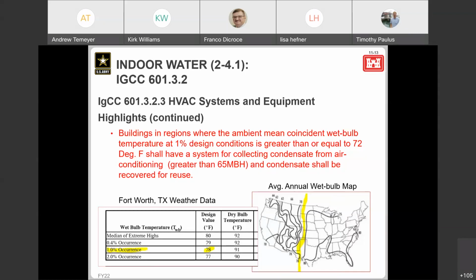The map shows the average annual wet bulb. This value is actually different than what is called out in red here in the body of the paragraph, because that is talking about the 1% design condition. But just for the sake of giving an example, I put a map on here with the average wet bulb temperature, and what you would see is that to the right of the yellow line are areas where there's a high likelihood of this criteria applying. The criteria is that if you have a 1% design condition wet bulb temperature greater than 72 degrees, and you're greater than 65 MBH, which is approximately 5.4 tons, you're going to capture the condensate for reuse.